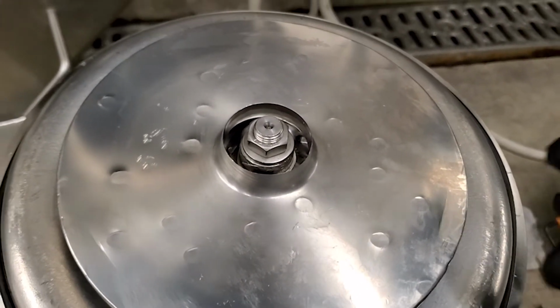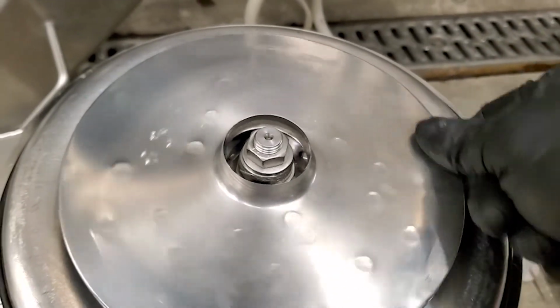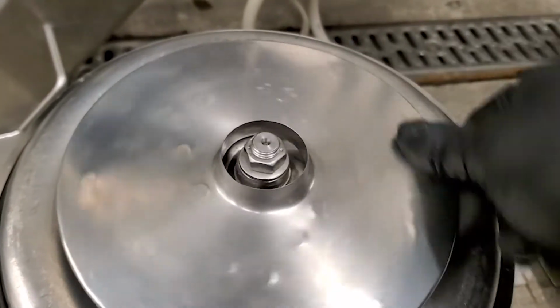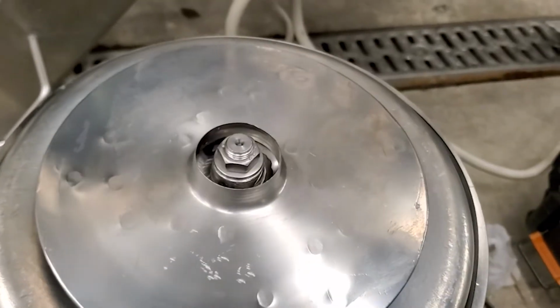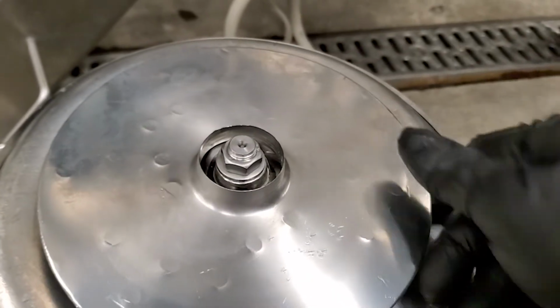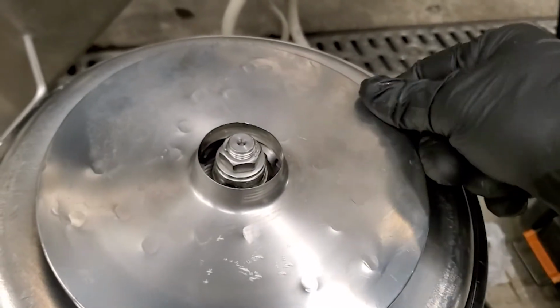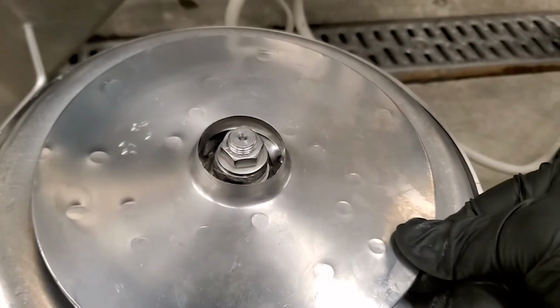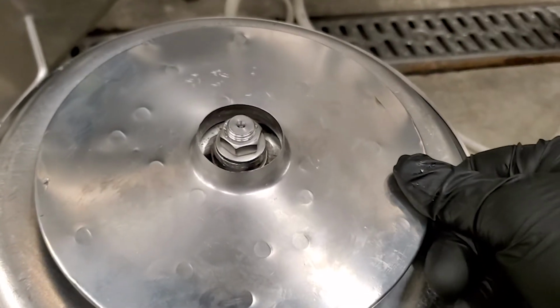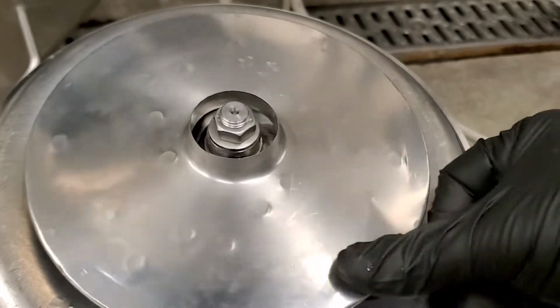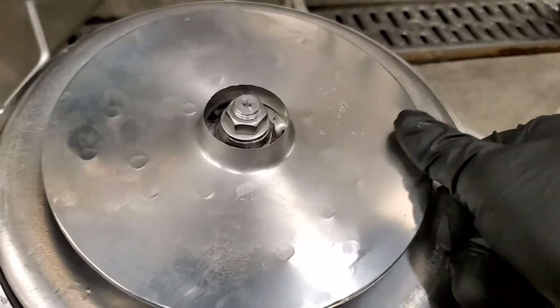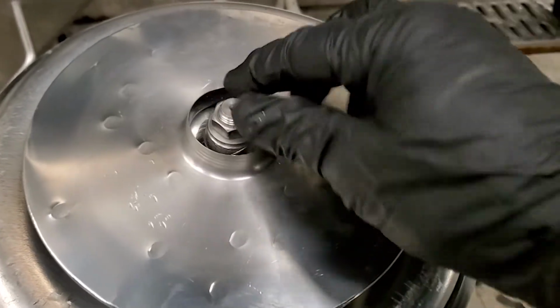If you go too tight on it, you'll notice this thing won't spin. You want it to just spin freely when you turn it by hand. If you tighten it down too much, you'll go to spin it and it'll only move a couple inches, and when you start up your pump you'll be able to tell it's struggling to spin that spindle. That means you've got to loosen this guy up.